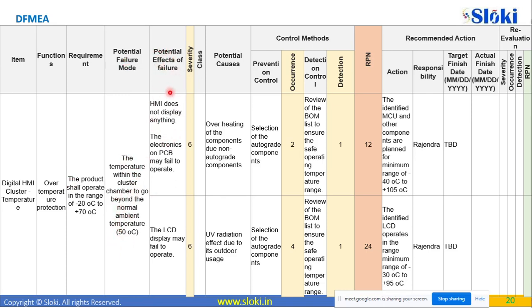What is the potential effect of the failure? The HMI does not display anything - the electronic PCB may fail to operate, or the LCD display may fail to operate. What is the severity? Out of a scale of 10, it's 6. That means if the HMI cluster doesn't turn on, the rider or driver will not die, so we don't give it a severity of 10 out of 10. It's just 6 - it gives discomfort, and some riders may feel panic if the cluster suddenly turns off.